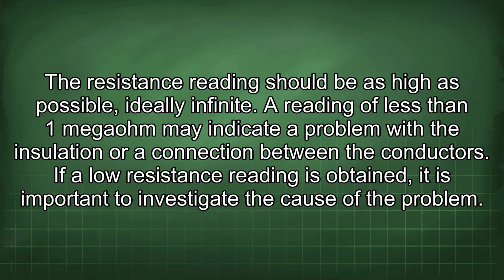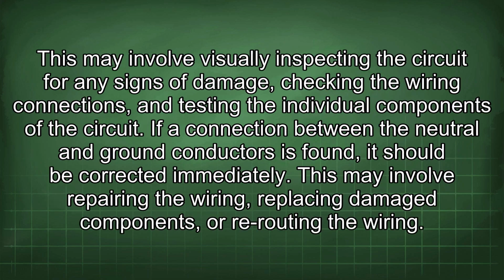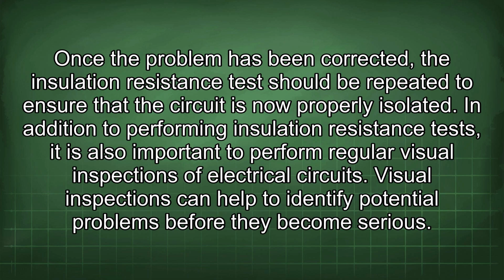If a low resistance reading is obtained, it is important to investigate the cause of the problem. This may involve visually inspecting the circuit for any signs of damage, checking the wiring connections, and testing the individual components of the circuit. If a connection between the neutral and ground conductors is found, it should be corrected immediately. This may involve repairing the wiring, replacing damaged components, or rerouting the wiring. Once the problem has been corrected, the insulation resistance test should be repeated to ensure that the circuit is now properly isolated.